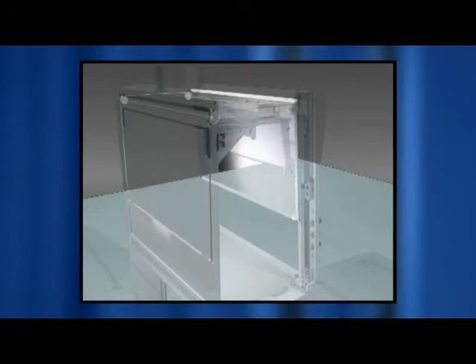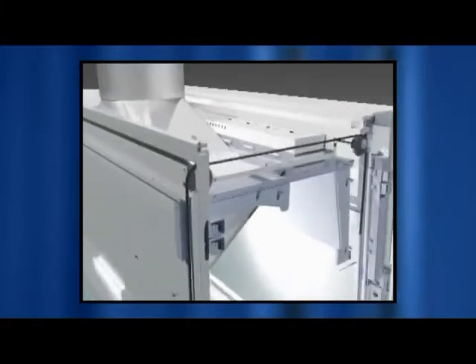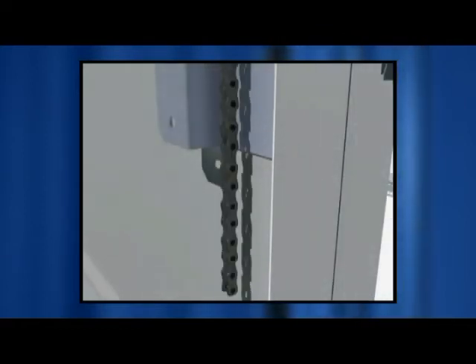The chain and sprocket system has increased durability compared to conventional sash mechanisms. In the event of a failure in the primary chain, a redundant dual chain drive causes the sash to tilt and therefore lock in position.